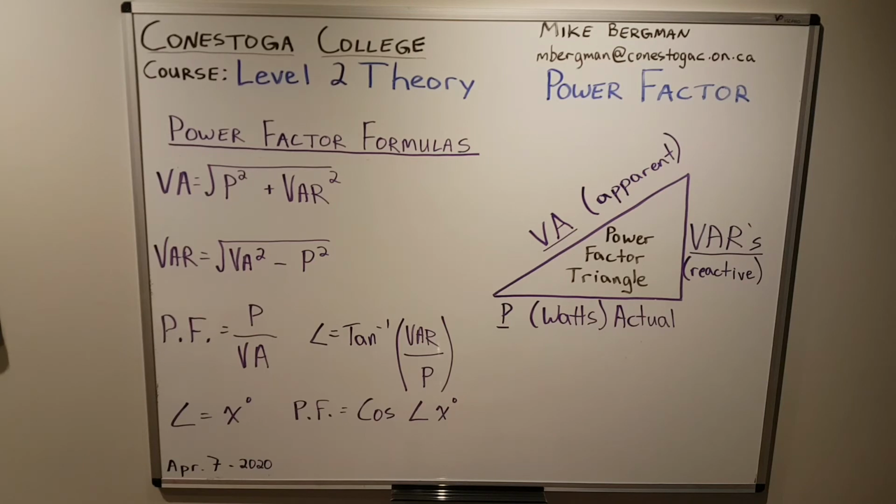So factories, you're talking about your largest factories, your Toyotas, your Linamars, they want to have a power factor of at least 90% efficient. So they're definitely going to have capacitors involved to correct their power factor. That way, they're not paying further costs because of how badly they're utilizing their power. So these factories, they want to know what their power factor is. It's as simple as taking your power, your watts, and dividing it by your VA.